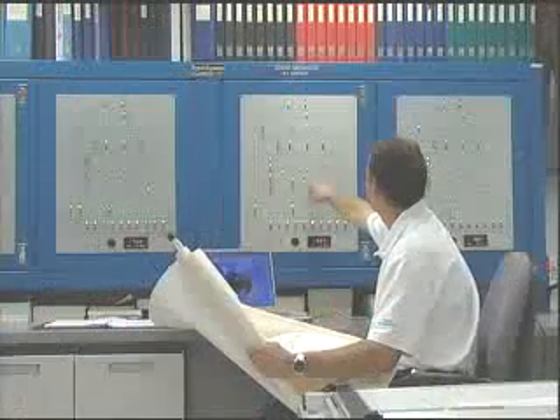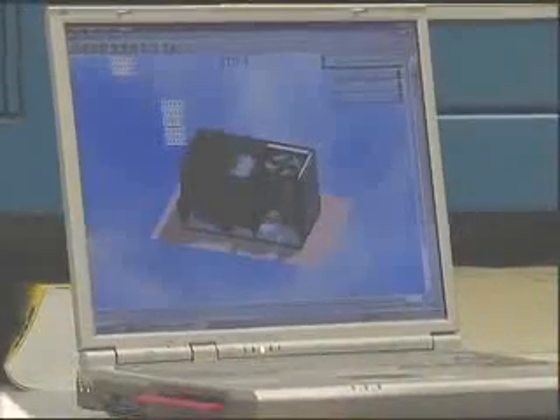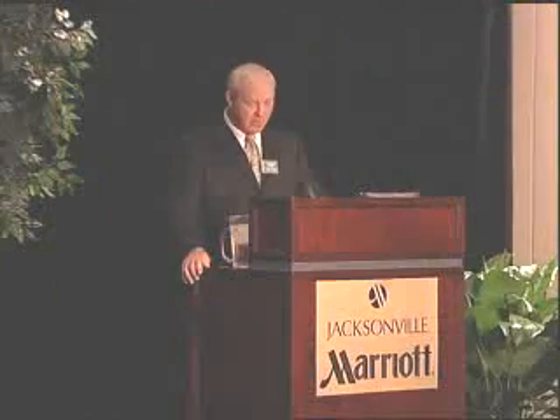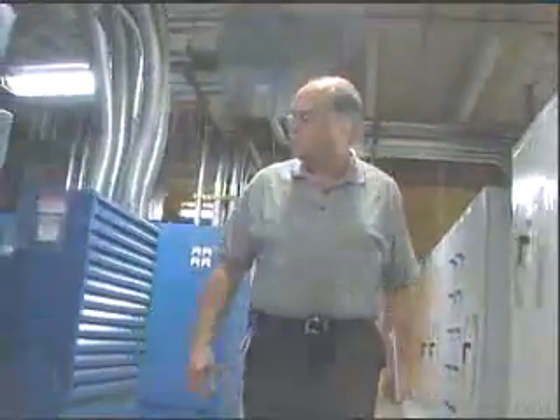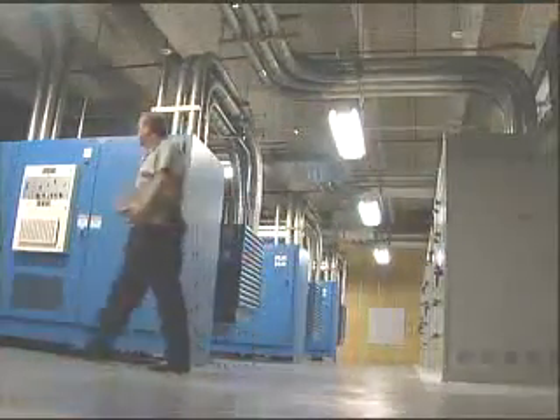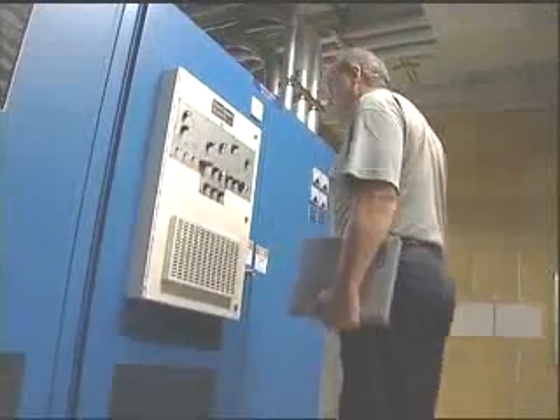Redundancy is incorporated into all facets of the power distribution system as well as the HVAC system, heating, ventilation, and air conditioning. There are 3 utility services. Any one of these is capable of supplying the total building power requirements. The primary feeder to the transformers is called a loop feeder, meaning that both the transformers are fed from both ends. Only low voltage enters the building.